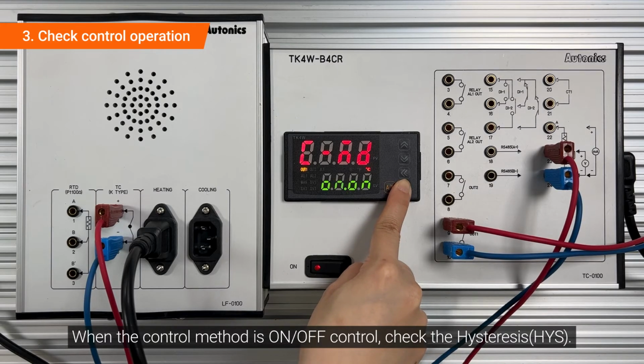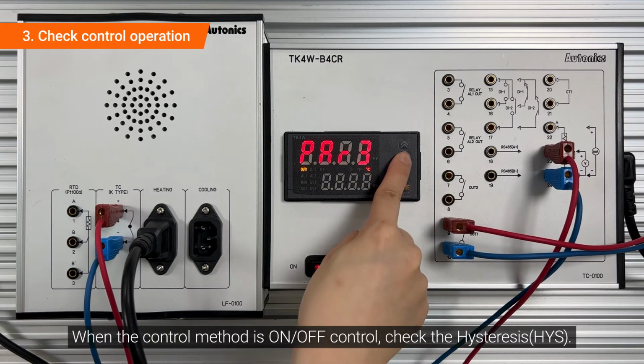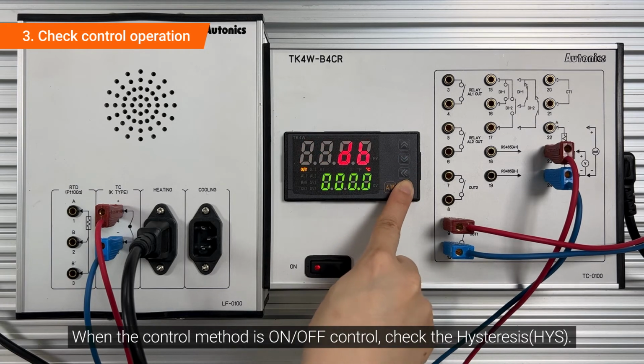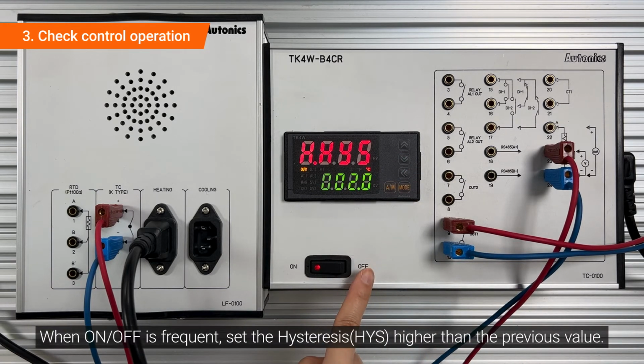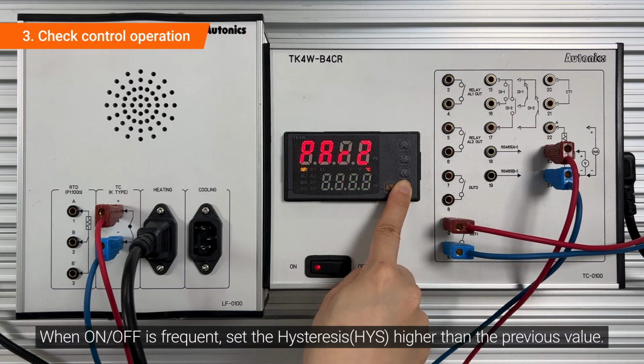When the control method is on-off control, check the hysteresis. When on-off is frequent, set the hysteresis higher than the previous value.